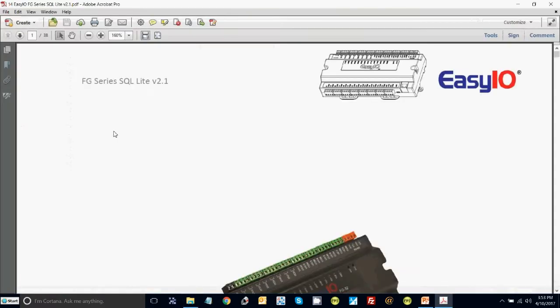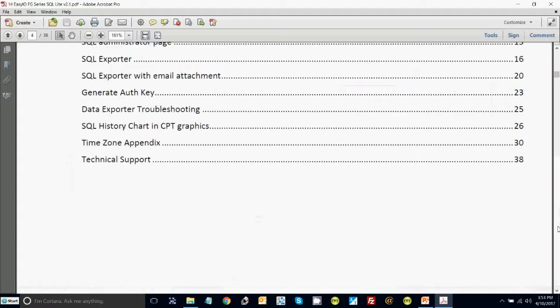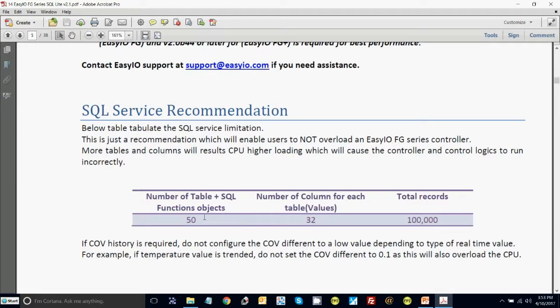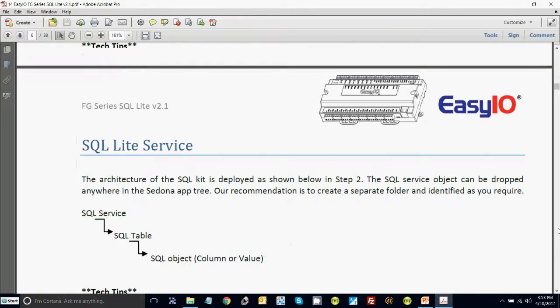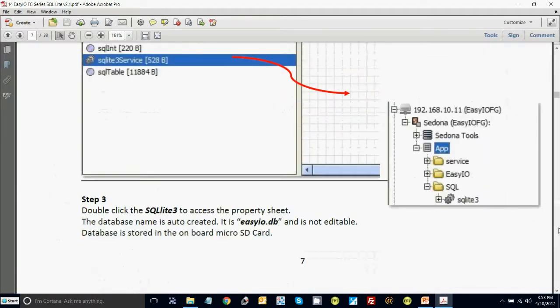If you look at this document it's going to tell you all the capacities — what it does. You can have multiple tables, you can have 32 columns per table. It tells you how many objects. You can also do some basic analytics in here — look at history, data mine the database, and take actions based on that for things like peak demand this year, this week versus this week last year. You could look at average temperatures, cost, all kinds of things.